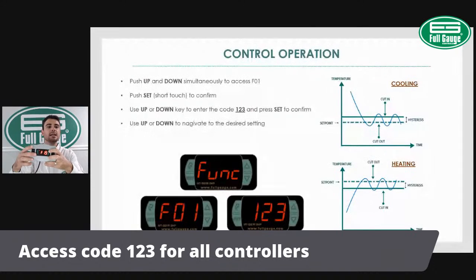That's another differentiation with the Full Gauge product line. All the functions are in a straightforward format. You have function 1, 2, 3, 4, 5, 6, 7. We don't do the menu and sub-menu that other controller manufacturers rely on. That just makes it complicated to set up. You have to keep going back and forth, and it provides a poor navigation experience. With our table-based programming, you get easy programming, and having the functions in numerical order allows you to easily identify which function has to be changed.